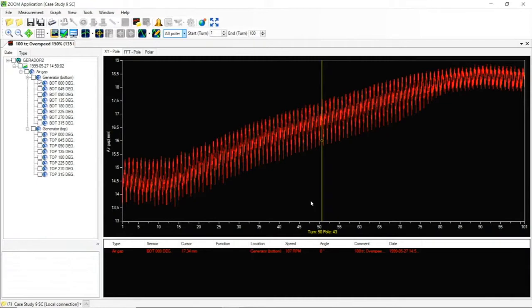Remember, this design was that above 99 RPM, the rim would float. We're above 99 RPM here, at 139 and going down, and 99 RPM is here. So at that point, the design said it should go back to a shrink fit—of course not instantly, but quickly. But if you look here, you can see the air gap increases at a much greater rate in this section than anywhere else. It's progressive, then you see a sudden rapid change in the delta.